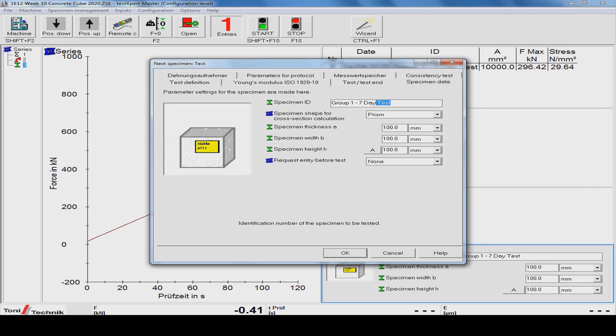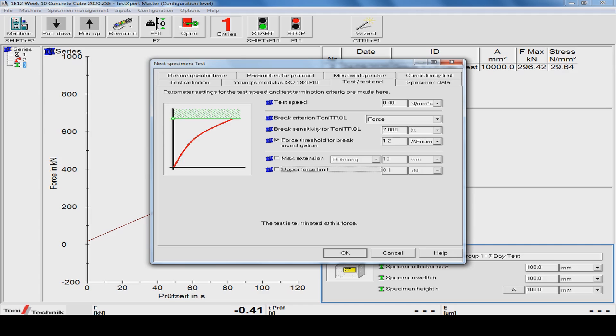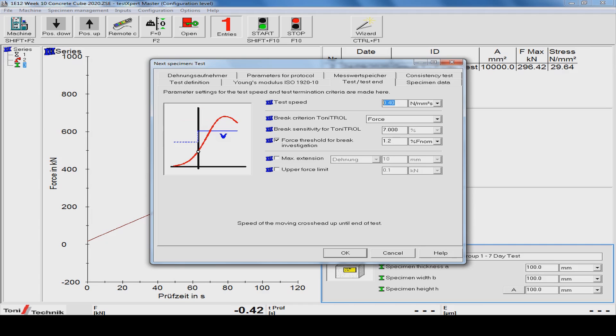Within the software on the testing rig computer, the sample ID and dimensions are entered. The desired testing rate in MPa is also entered. In this case a rate of 0.4 MPa will be used, as per the standard.